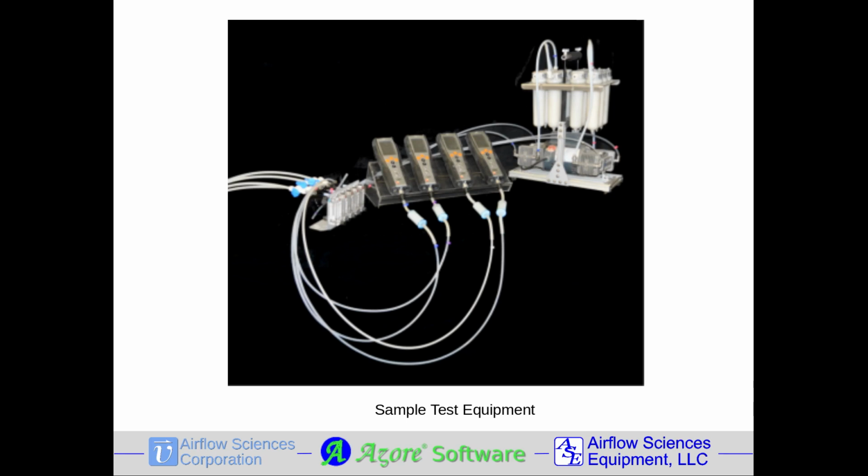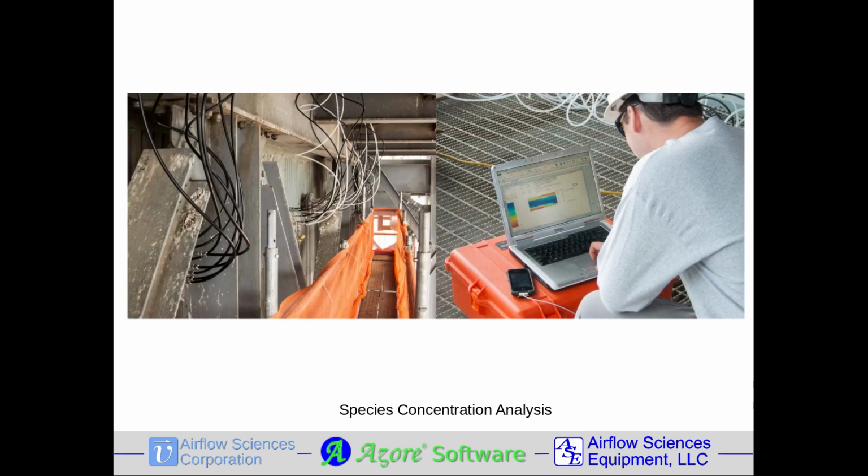Field testing personnel measure the SCR performance by utilizing a variety of different testing kits. Often a mobile kit will contain gas analyzers, conditioners, pumps, and tubing to quickly and easily integrate with the existing SCR gas sampling grid. A ruggedized computer with custom software is used for analyzing and visualizing the ammonia profile in the SCR.